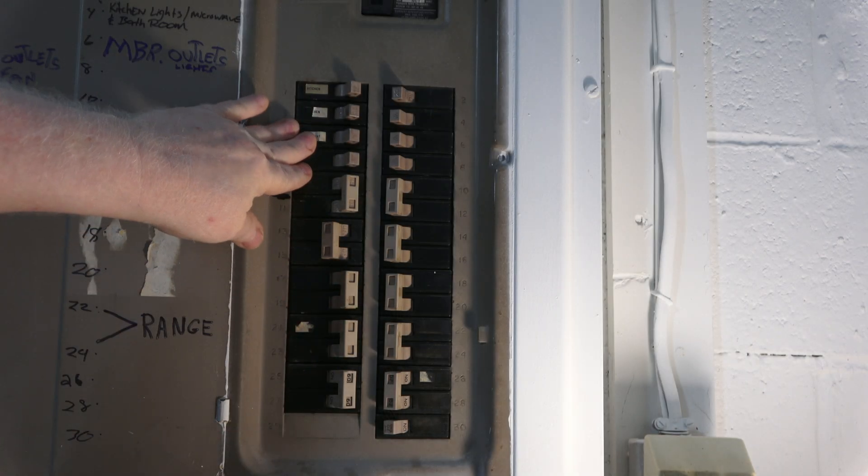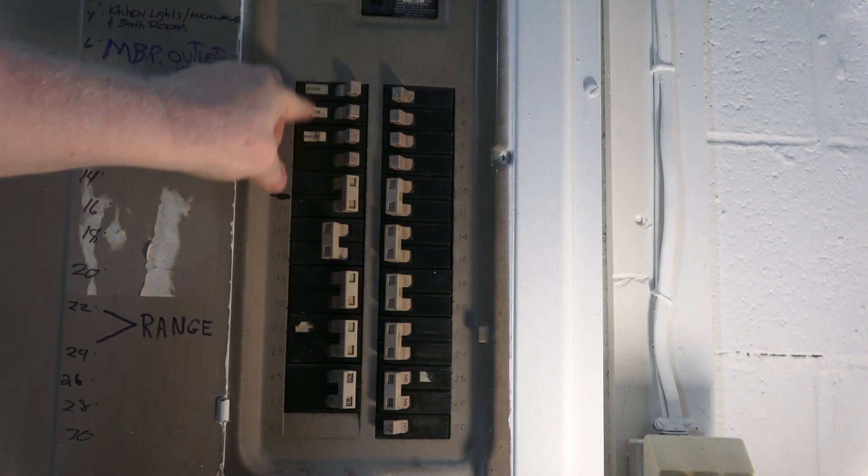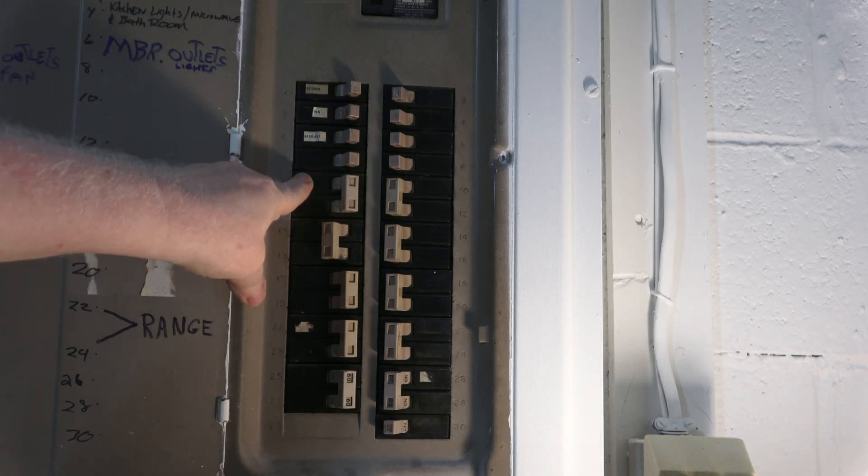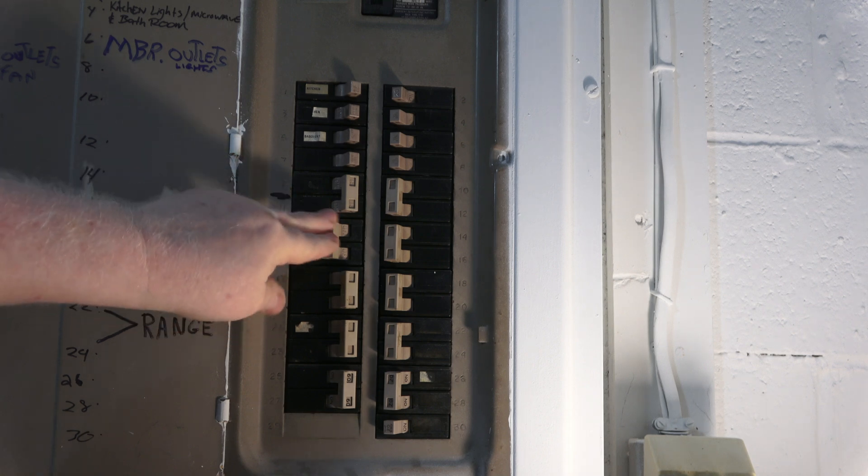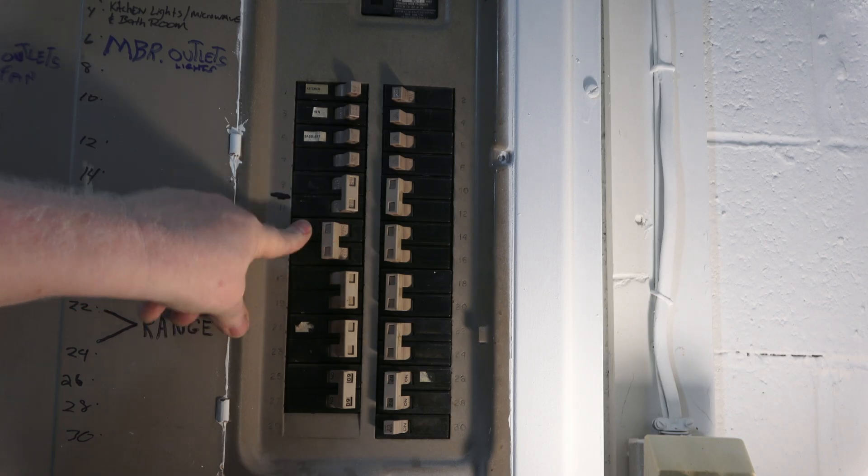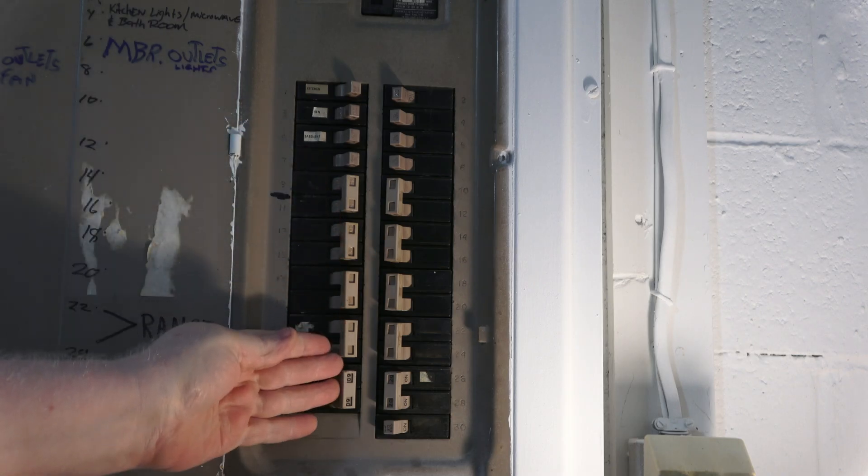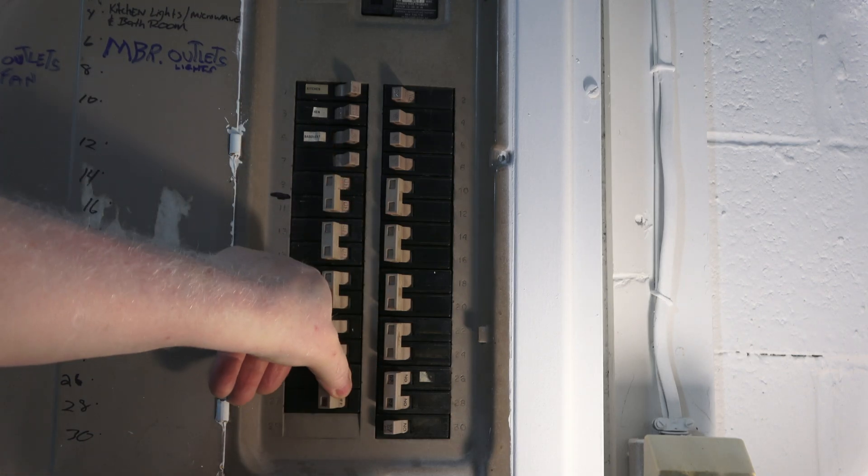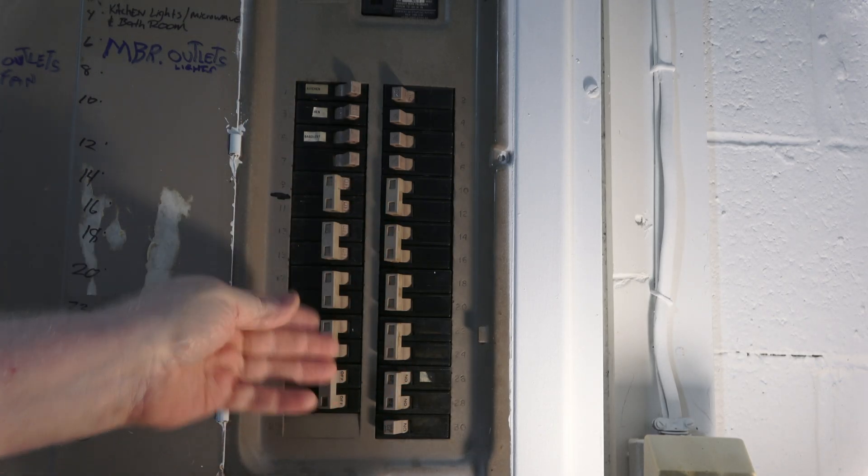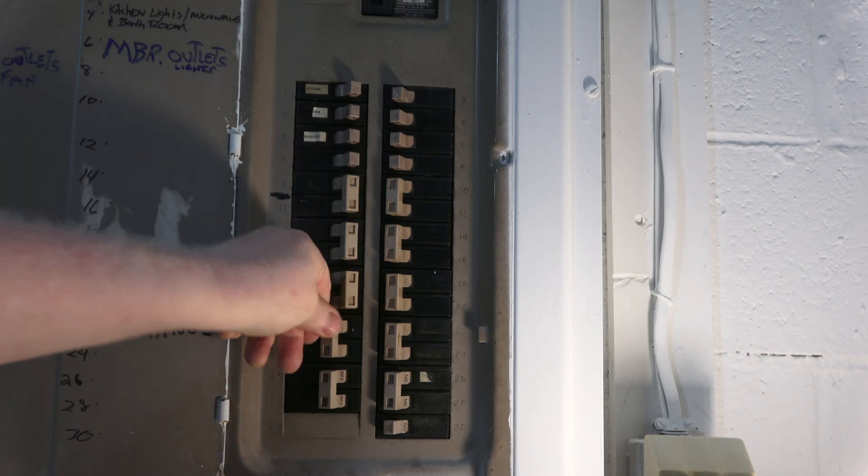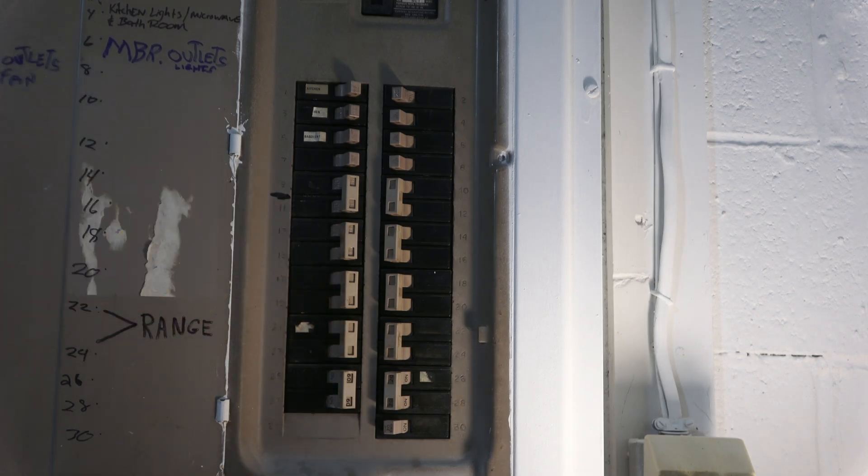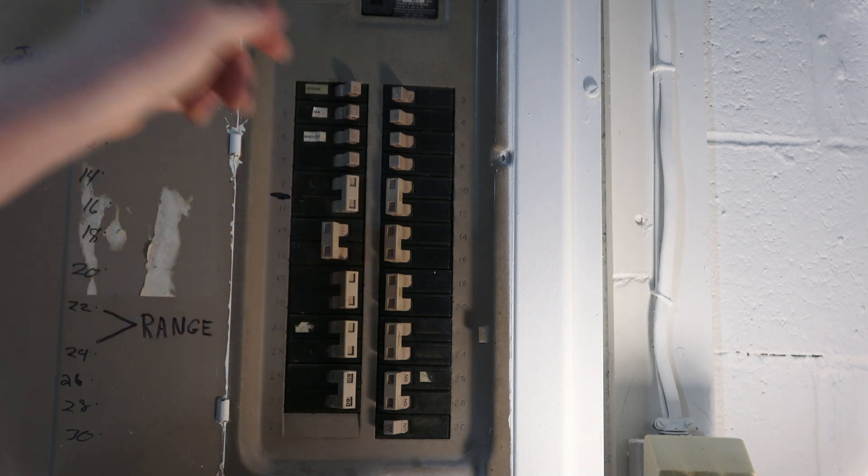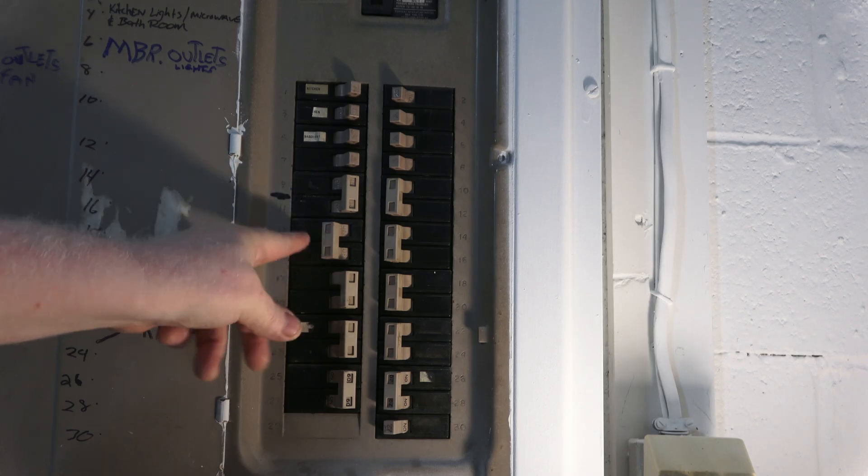Quick overview of the electrical panel. These are single throw breakers, which means you're dropping 120 volts on each wire. These are double pole, 120 volts, 120 volts. And that's the two wires that operate your heater. And all these double poles are 220. I know this is the one for the baseboard heater. But if you come down here and you were unsure which breaker to turn off, turn off all the 220s. And there's a whole list here. You turn them all off. Then go check for power. That's an easy way of doing it. However, I know it's this one. So all these can be on. And I'll show you the example. Listen for the beep. The beep went out. So this one is the one that operates the baseboard heaters and the thermostat.